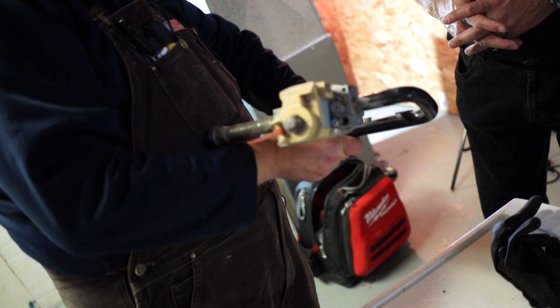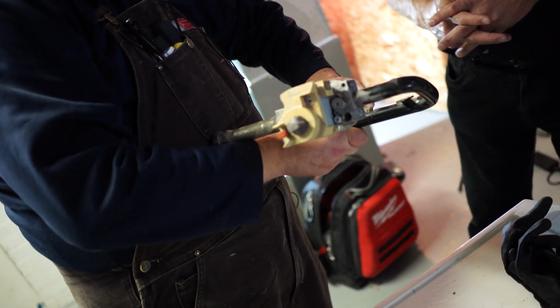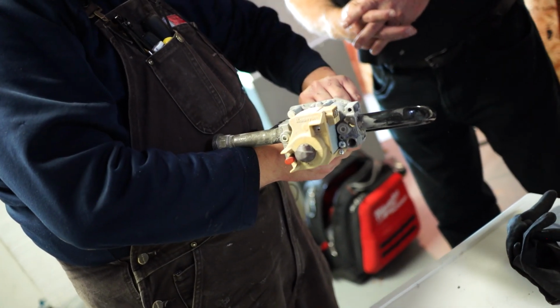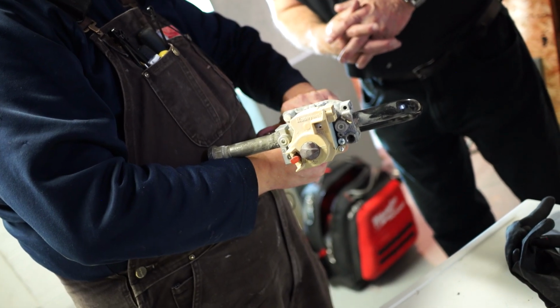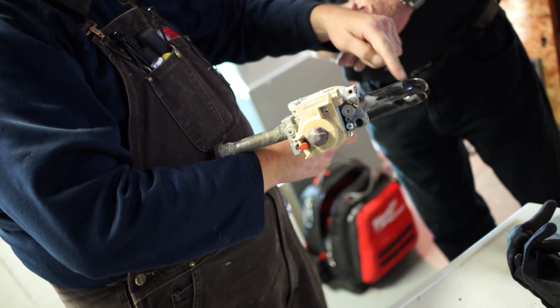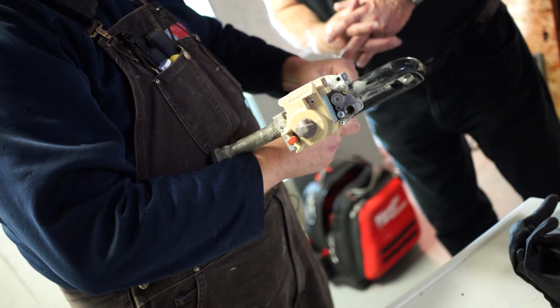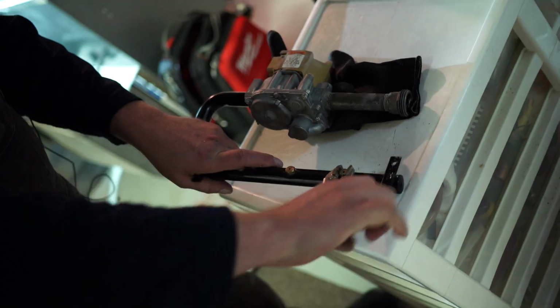So what are we doing here? Well, this is the burner that's not firing. You just pulled that one out? Yeah, you have to pull the whole rack out, just for ease of access. So basically the tube is where the gas travels through, and the orifices are what actually let the gas up to ignite.